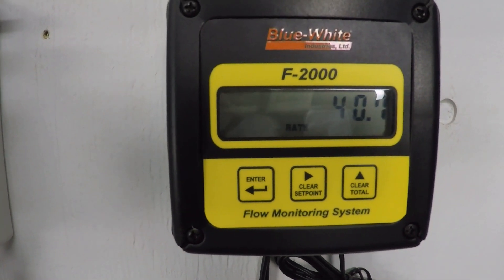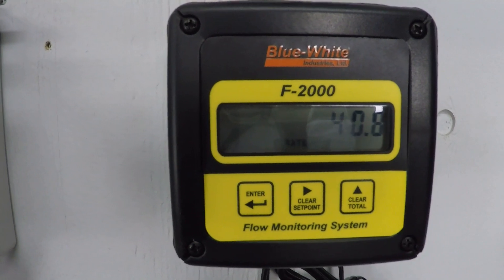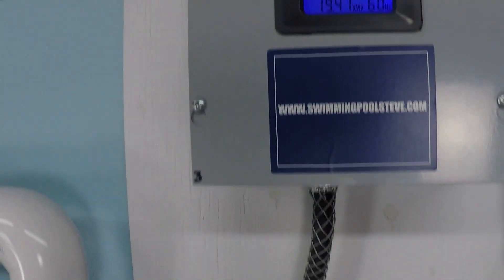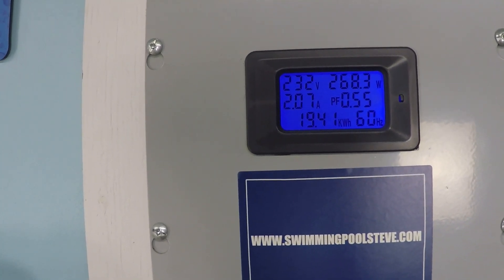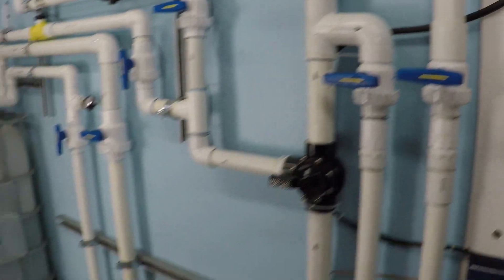At 2,000 RPM: readings of about 40.5 to 40.8 — calling that 40.7 gallons per minute. Power is 268.5 watts, just over 2 amps at 2.07 amps current draw.